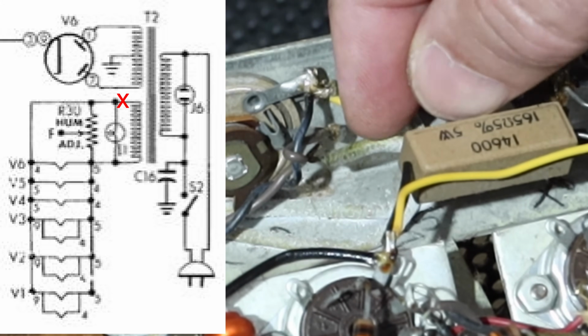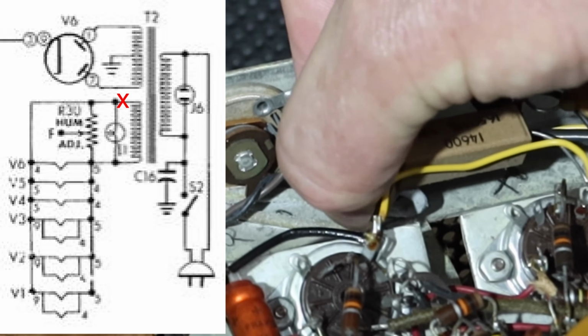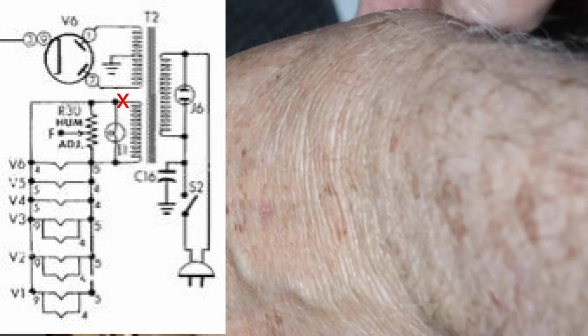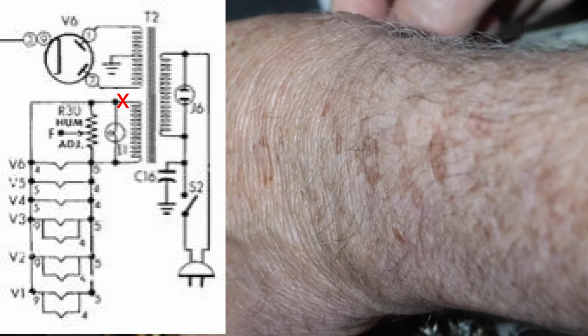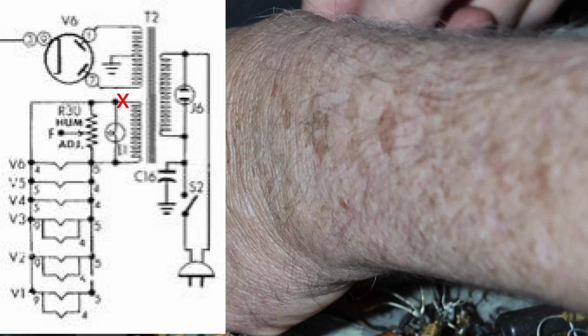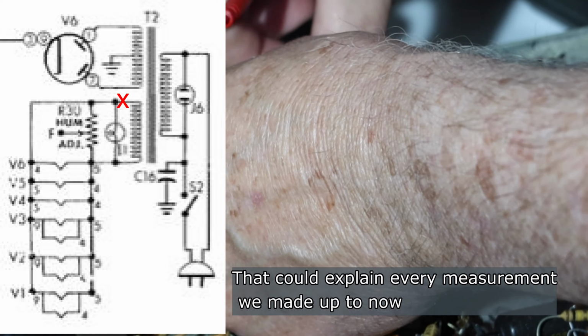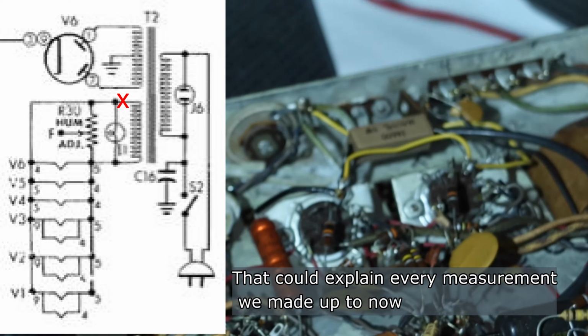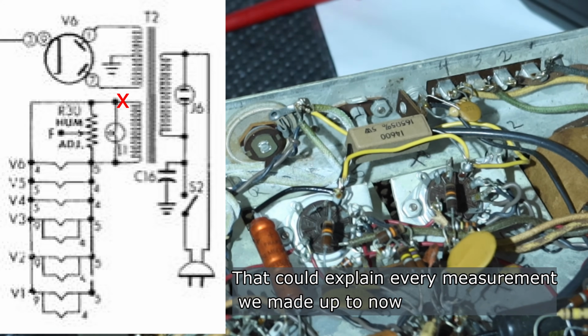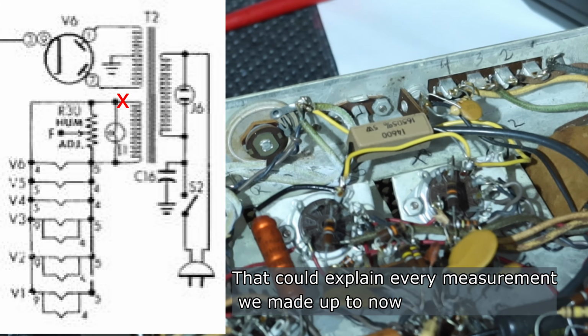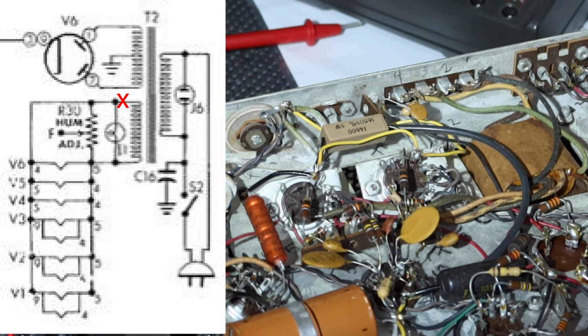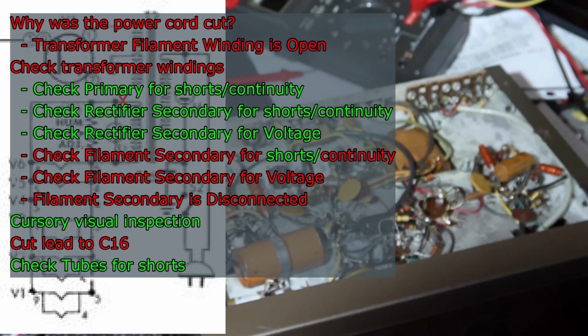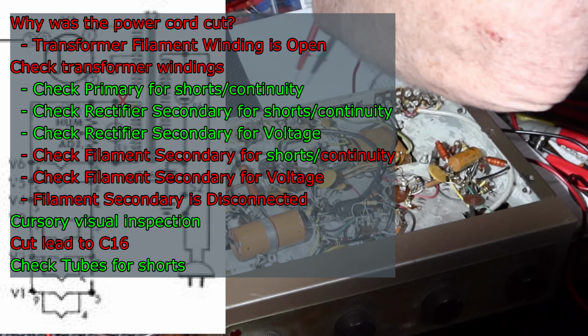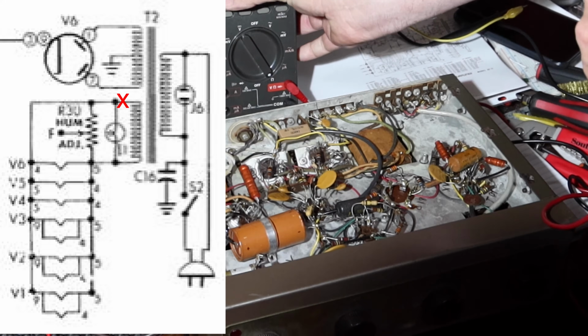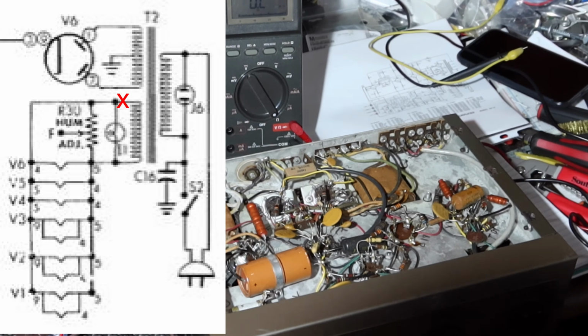I'm thinking about trying to see what we have in terms of coil resistance. Now that I know it wasn't connected, well, that might be our open winding, right? It's an open connection, because this isn't connected to that brown wire. So let's do a resistance measurement and see if our winding is really open or if it just wasn't connected. Would somebody have cut the wire off and put this in here without realizing the solder connection had come loose? Let's see.